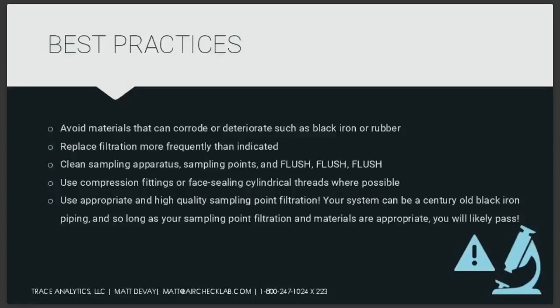Always clean your sampling apparatus, your test kits, your sampling points, and flush your system before you take a sample. A lot of these problems can be avoided if you just let that system run at full flow for a good 10 or 15 minutes before you take a sample. As mentioned before, compression fittings and face sealing cylindrical threads are going to be your go-to if you're trying to avoid contamination in your unions and fittings.